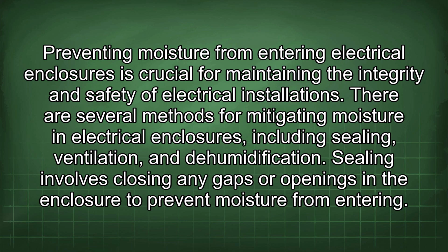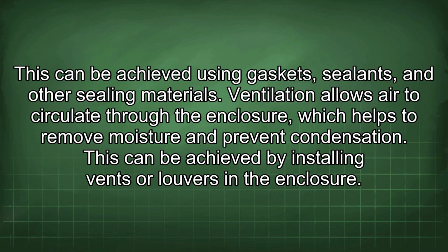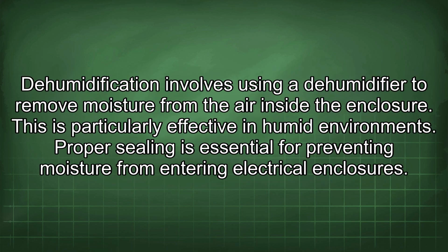Sealing involves closing any gaps or openings in the enclosure to prevent moisture from entering. This can be achieved using gaskets, sealants, and other sealing materials. Ventilation allows air to circulate through the enclosure, which helps to remove moisture and prevent condensation. This can be achieved by installing vents or louvers in the enclosure. Dehumidification involves using a dehumidifier to remove moisture from the air inside the enclosure. This is particularly effective in humid environments.